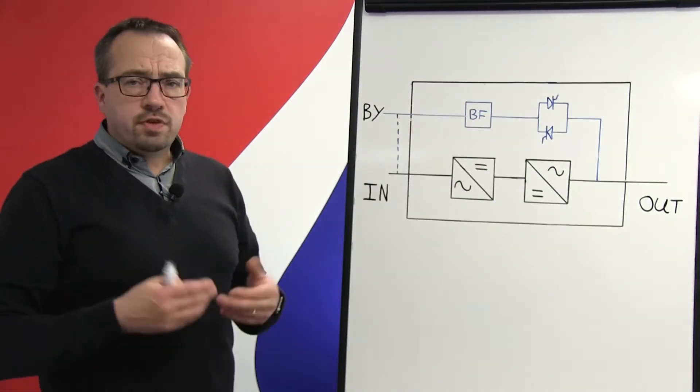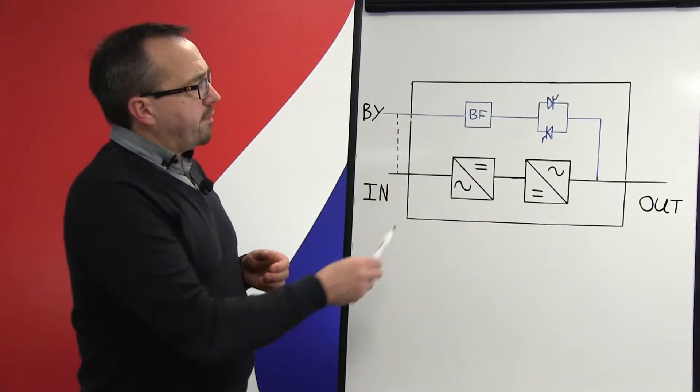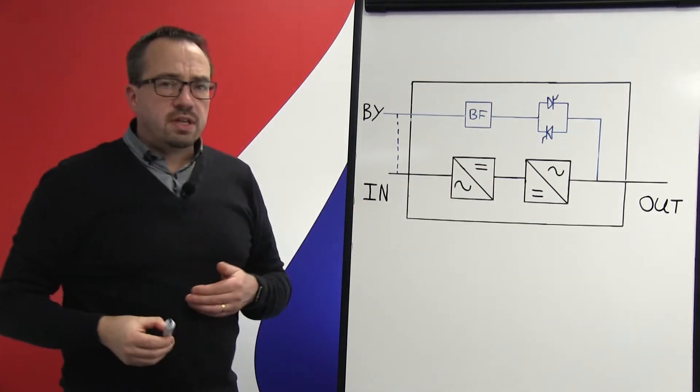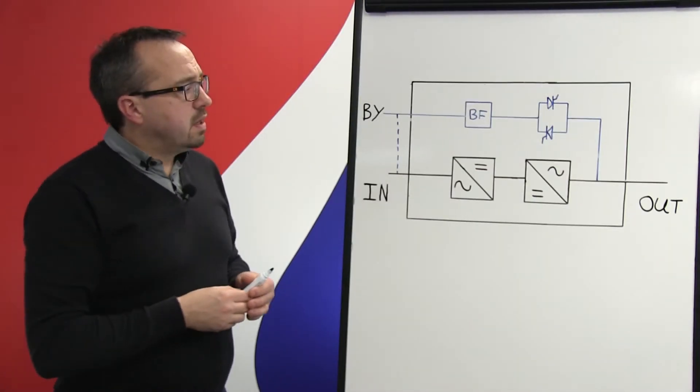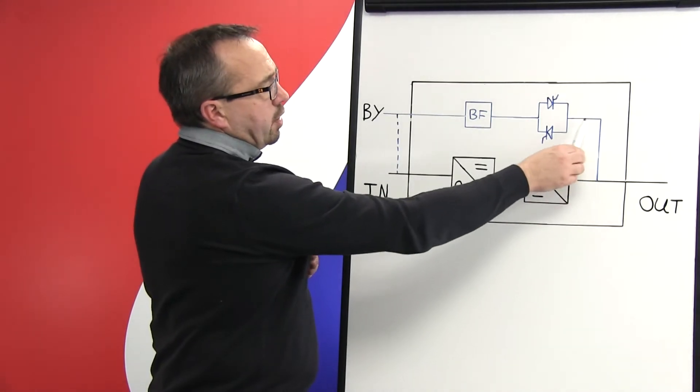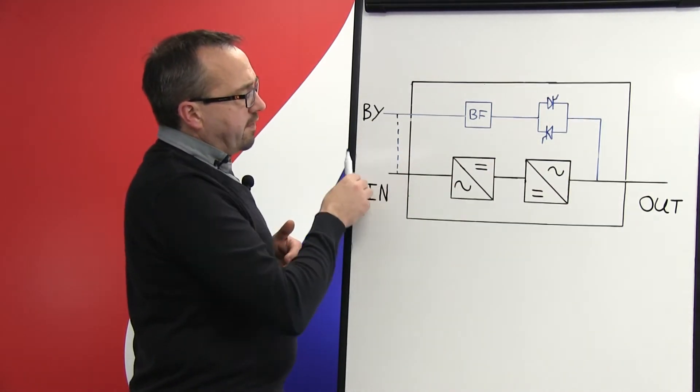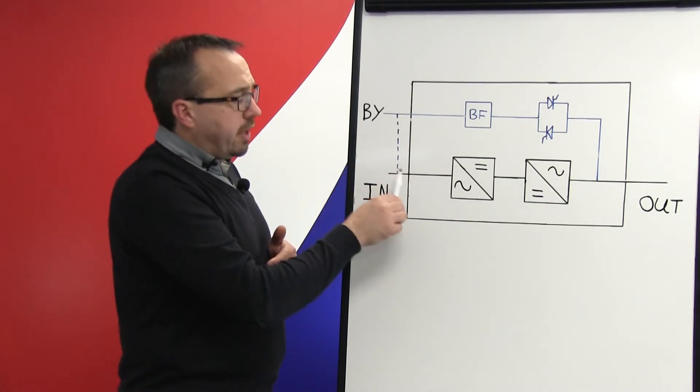Now the bypass itself is made up of two primary components: you have the back feed protection and you have the main static switch. The back feed protection is basically there to prevent the UPS system from back feeding power through the bypass line when there's no main supply.